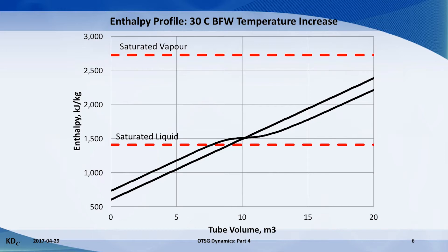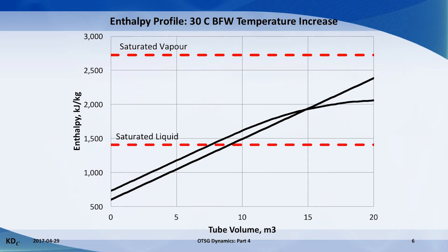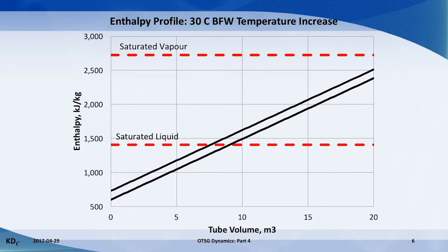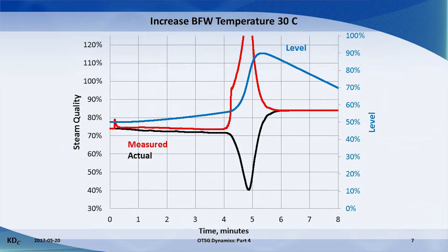The hot front pushes through the boiling point, and a slug of water is fired down the OTSG like a cannon. The outlet enthalpy quickly dips low because of the extra mass of water, and then snaps high to the expected value. The trend of actual and measured steam quality illustrates the effect of this extra mass leaving the OTSG.